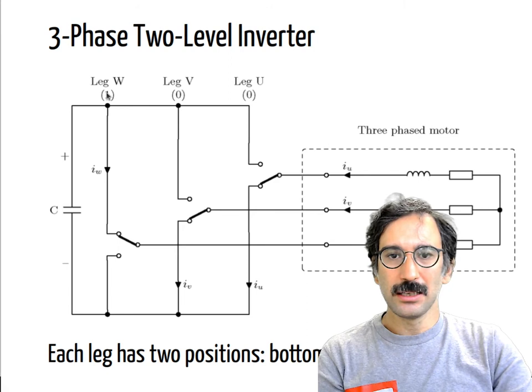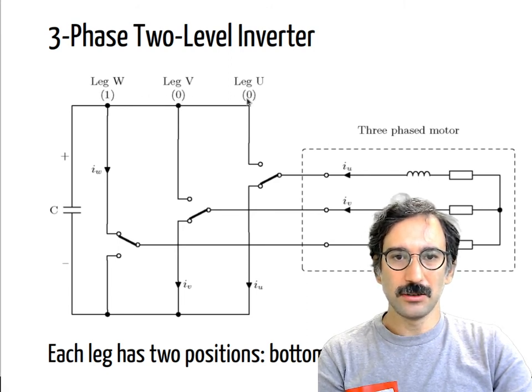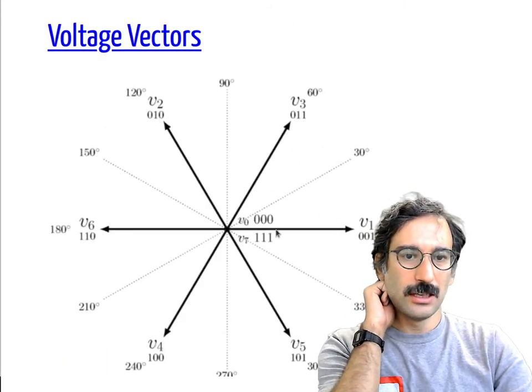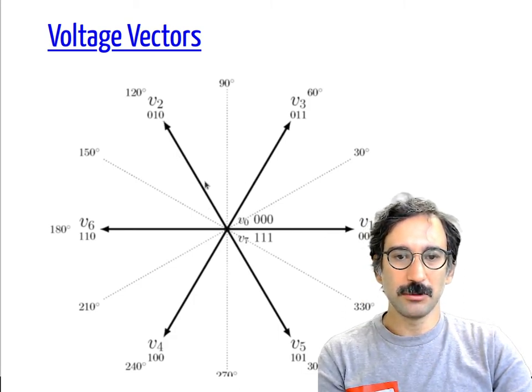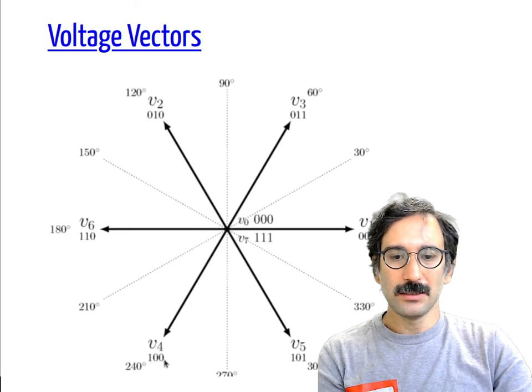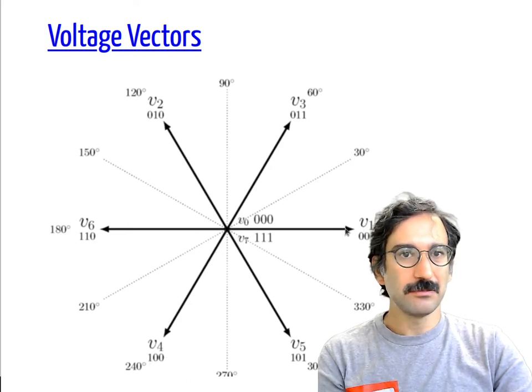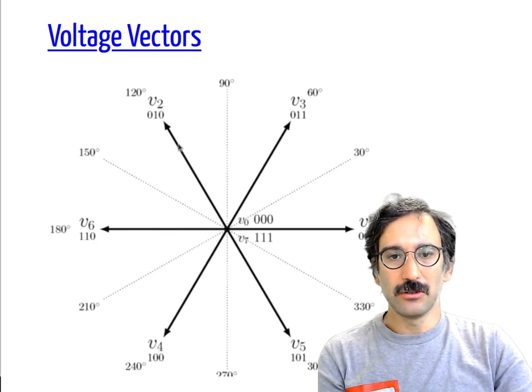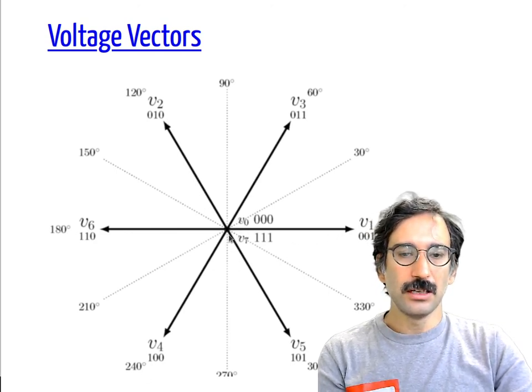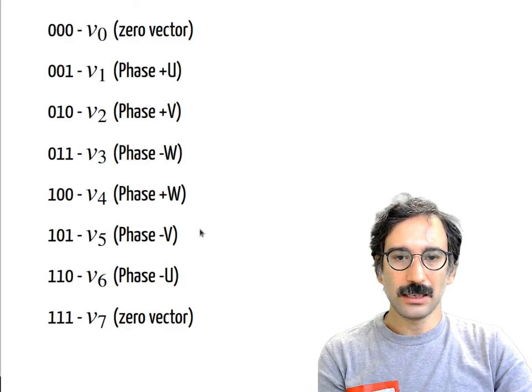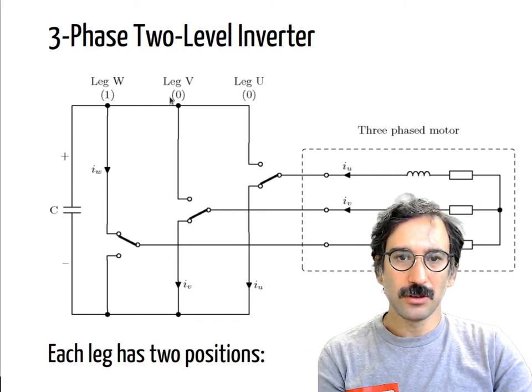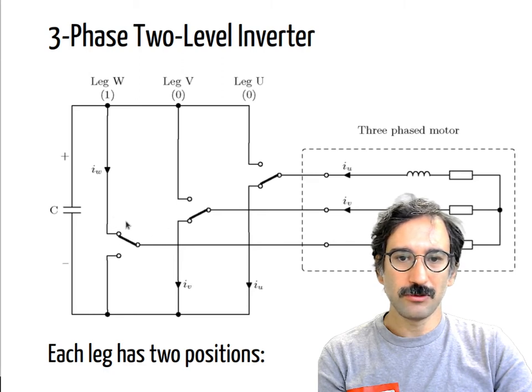Similarly, I can apply zero-one-zero or one-zero-zero. At zero-one-zero, the MMF direction is 120 degrees away. To get the reverse MMF direction of zero-zero-one, instead of applying zero-zero-one you apply one-one-zero: both phase B and phase C are connected to positive, so they will each have plus I over two, while only phase A is connected to the bottom position.